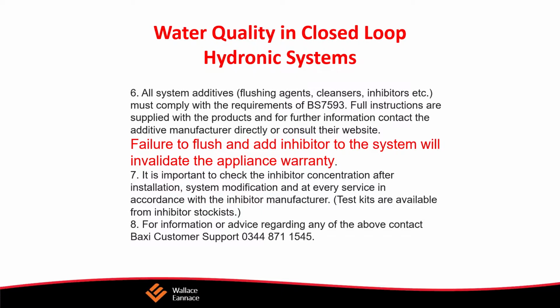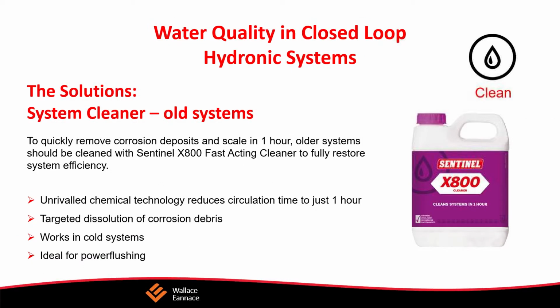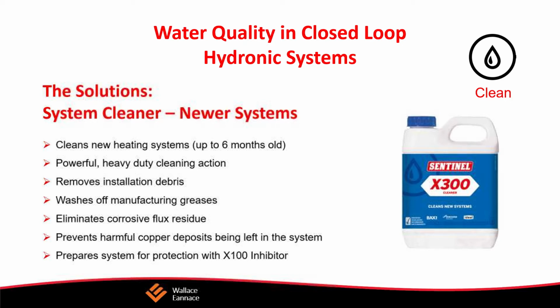So in a closed loop hydronic system, looking at these, look at the interior of these pumps, you can see all the buildup of scale and corrosion inside these systems and inside these pipes. And you can imagine what this is doing to the flow and changing the characteristics of the pump, of the flow through the system, regardless of what the pump is doing and the behavior of the pump relative to its original install. So you're going to cause general corrosion, pitting corrosion, the buildup of sludge, biofilms. You can have blockages and scaling. These are going to cause failures, and it's going to reduce efficiency.